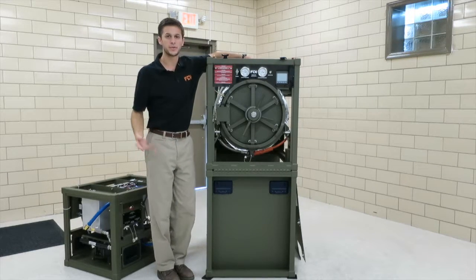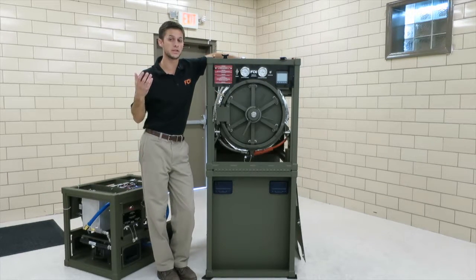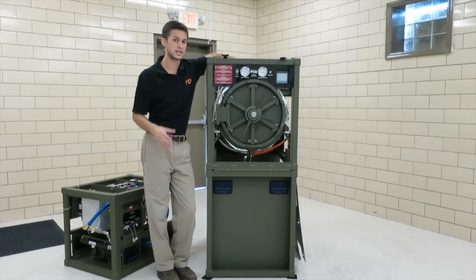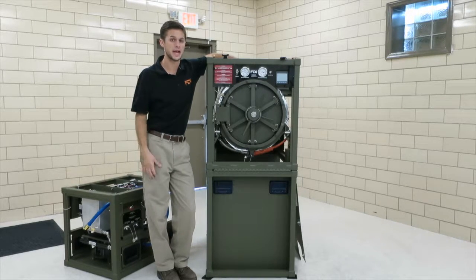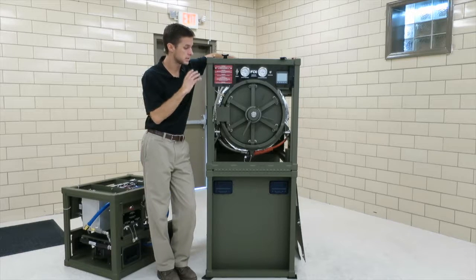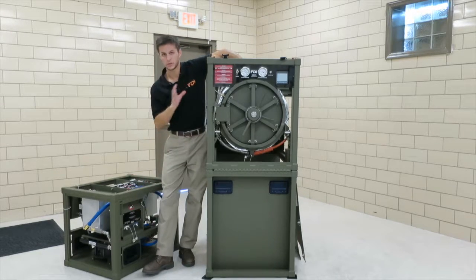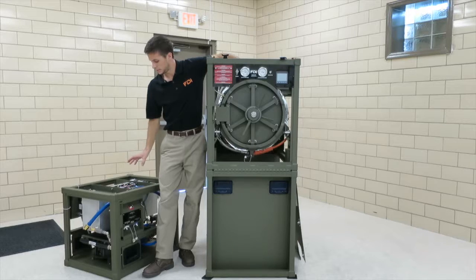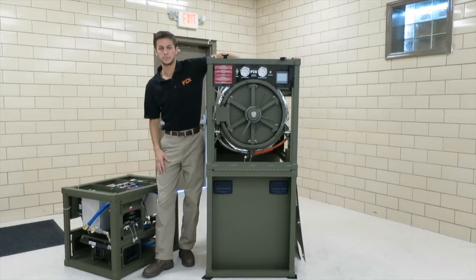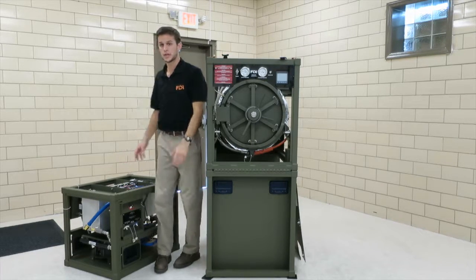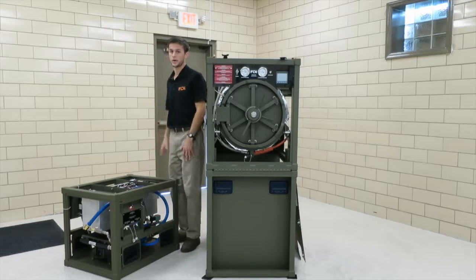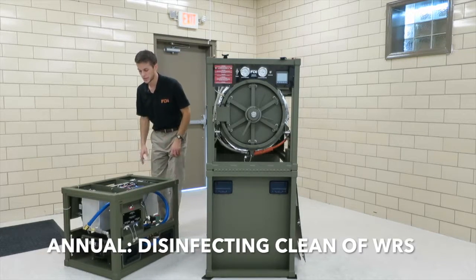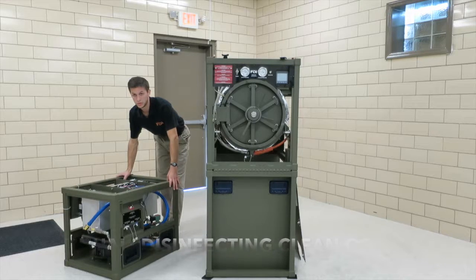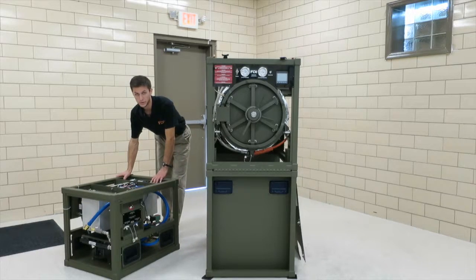So lastly, for preventive maintenance is what to do annually, and this is actually an FDA required task. When we got this thing certified by FDA, there's a few things that they require to allow it to be FDA certified, and one of those is a disinfect and clean of the water recovery system. So annually, you're going to want to perform the disinfecting clean of the water recovery system. And this complete task is in another video.